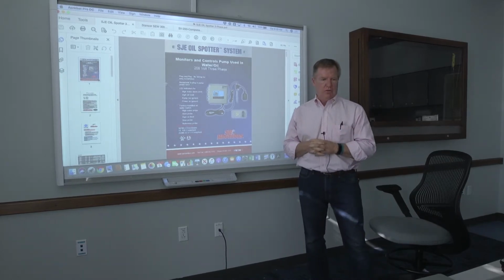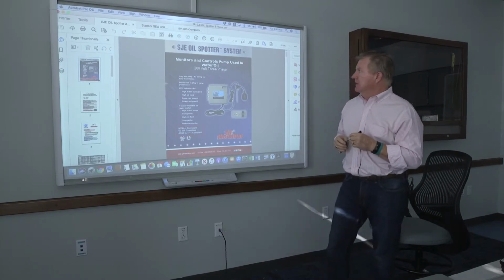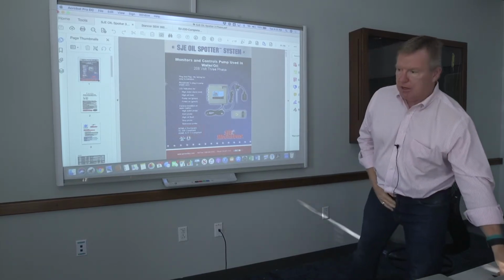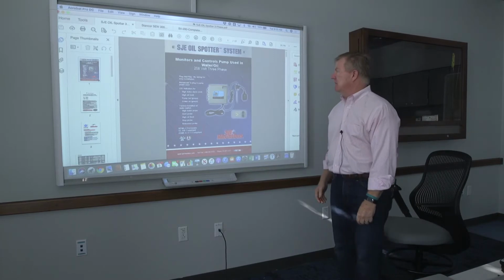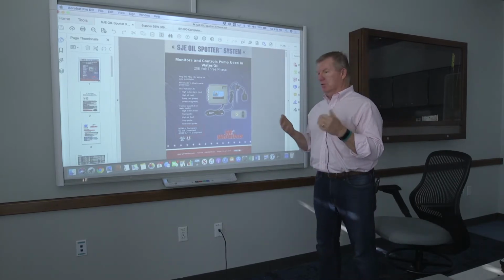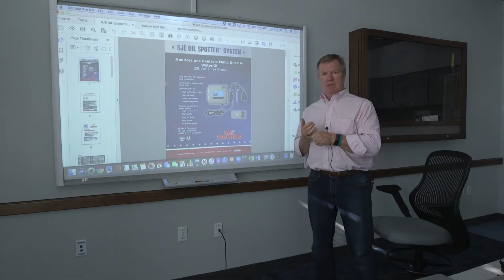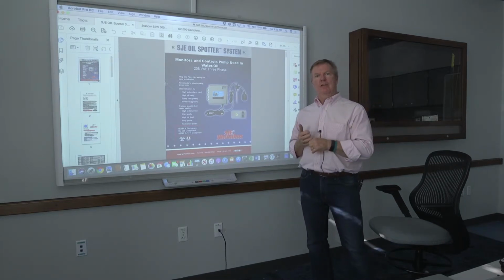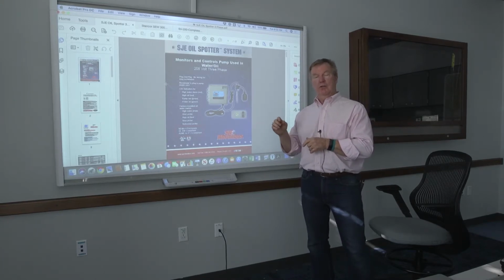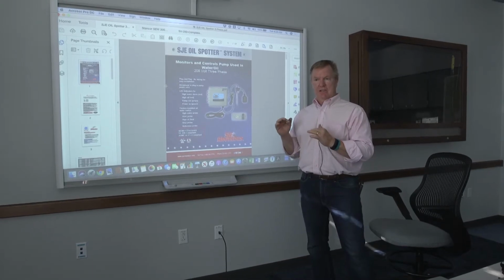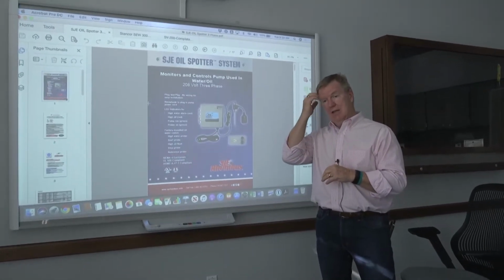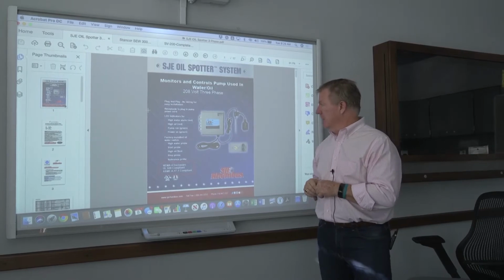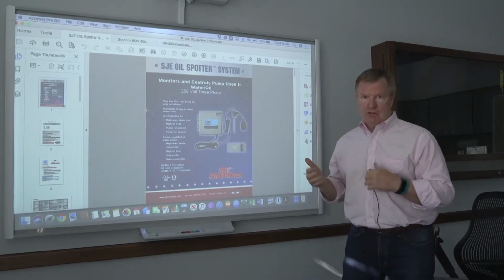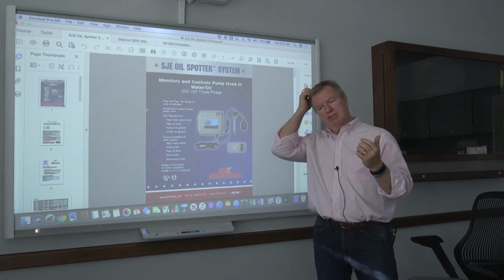I'm going to talk about the sump pumps in the facility and the sump pump controller today. The oil minder, oil spotter sump pump that's in the facility is designed for two purposes. One is to pump out water in the pit when it appears, and it also recognizes when there is oil on top of the water so that it does not pump the oil to the drain in the operation. Let me go through. First of all, I'm going to talk about each of the sump pumps.